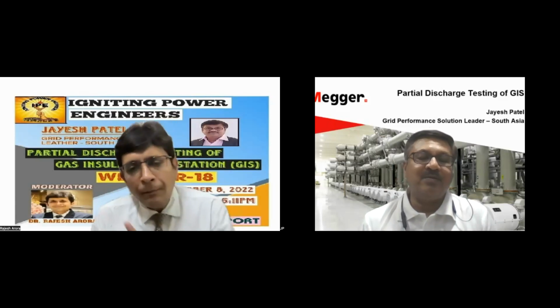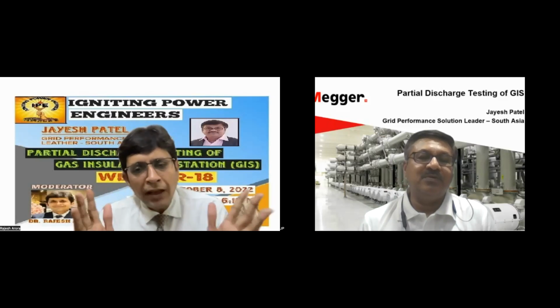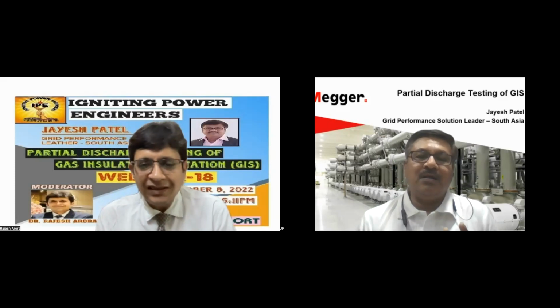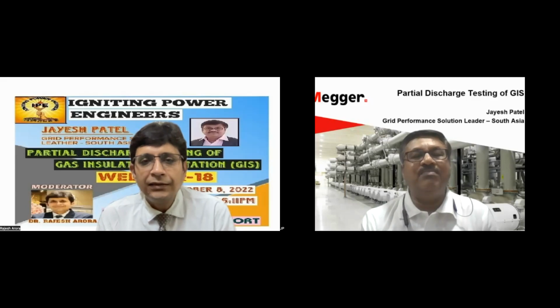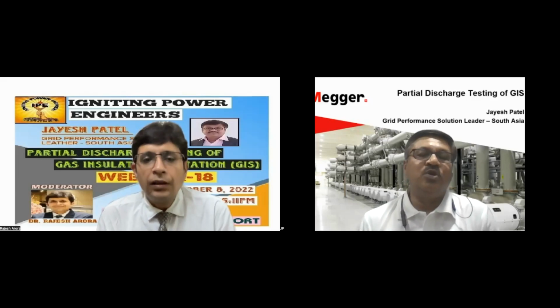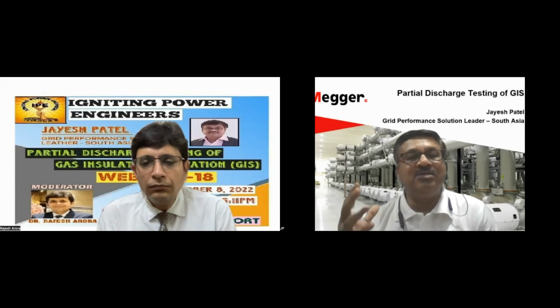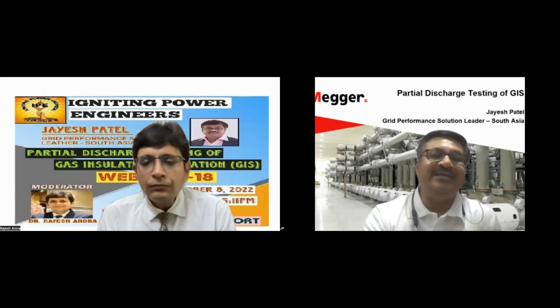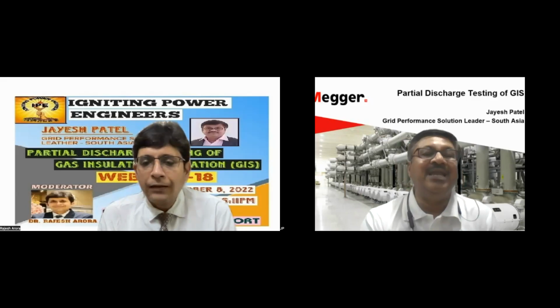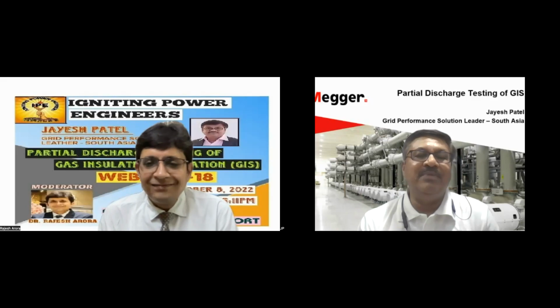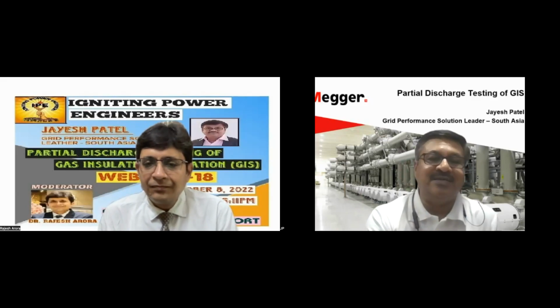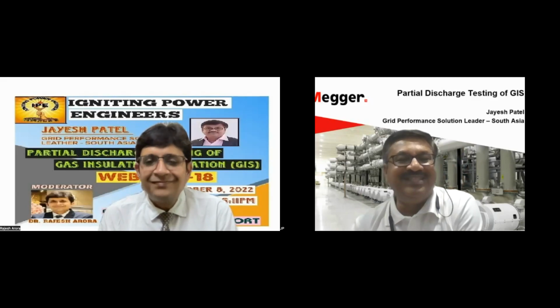Will it take care of the PD in the entire cable, or to some extent? To some extent, it will measure, because a cable is a long piece of equipment. So if the PD pulse is good enough and it is traveling till the UHF compartment, then it will take care of it. Because ultimately the signal should reach a sensor. The sensor is not going to walk down to the signal.